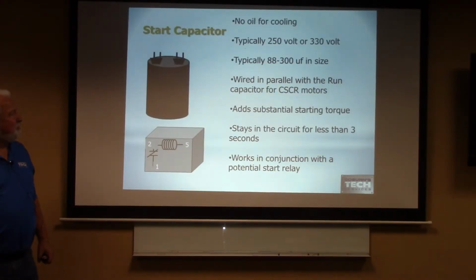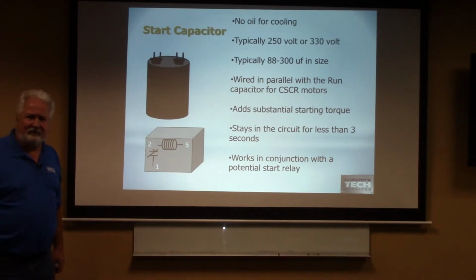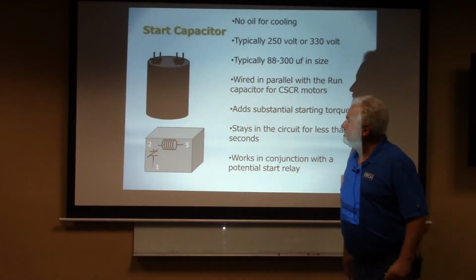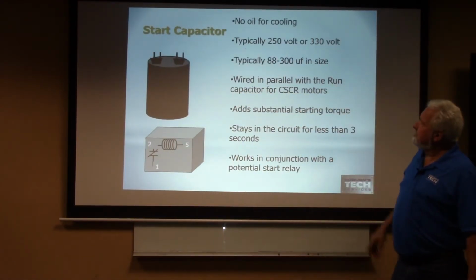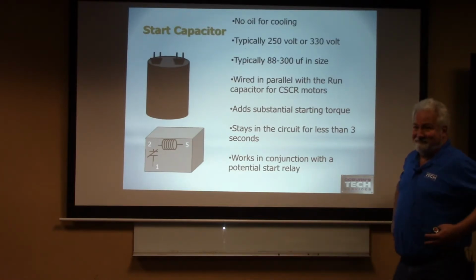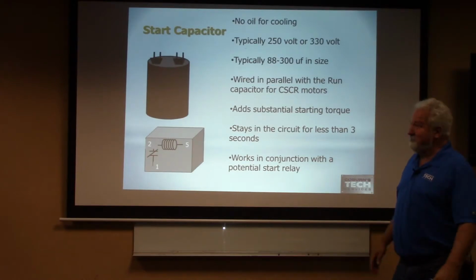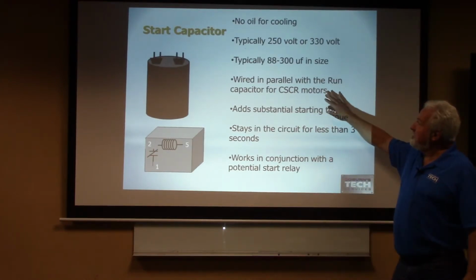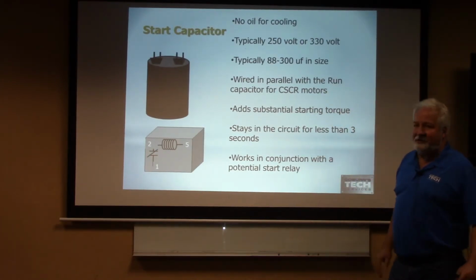Oh, what is this? What kind of capacitor is that? Start capacitor. That's different from what we had a while ago. We had him out there push starting that car. This is a start capacitor. It's typically 250 or 300 volt, typically 88 to 300 microfarads. What happened to our microfarads? Big microfarads. It's wired in parallel with the run capacitor.